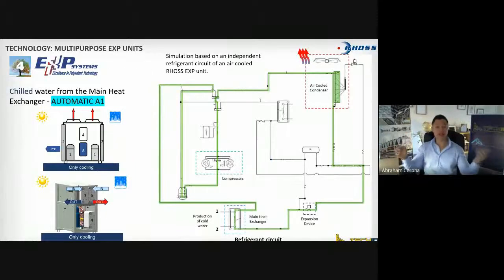So, scenario 1, as I say, we have automatic and select mode. We are in automatic mode when we are prioritizing the generation or production of chilled water, and we have 3 modes: automatic 1, automatic 2, and automatic 3, that we're going to be defining in different ways. All right. On the left, I still have what I like to call the old school, how factories used to show this. And they are telling you in automatic 1, we're producing only cool water by the main heat exchanger.